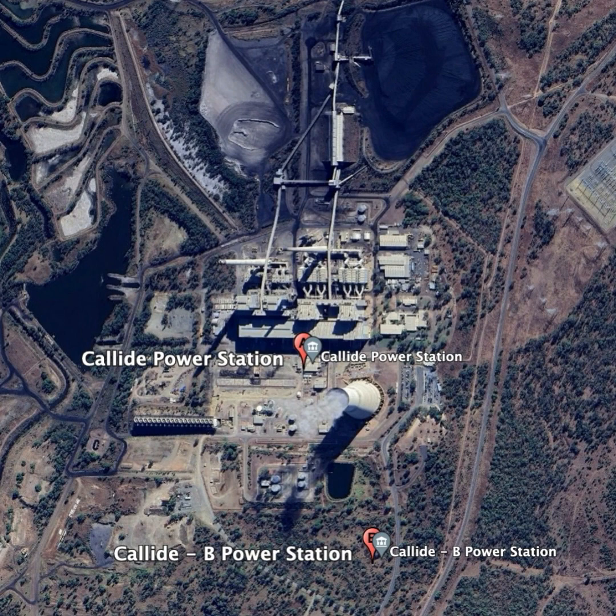The generator was now experiencing high temperature arcing between the rotor and the stator, ionizing the copper, and was now sinking 300 megawatts and 1400 megavars from the grid, which was 3 times its actual power rating. This dragged down the line voltage at Callide substation, resulting in reactor and capacitor banks being switched in to compensate. Callide Unit B2 then also tripped. After 40 seconds of arcing in Unit C4, a phase-to-phase fault dropped the A and B phase voltages severely at the Callide substation. The following events happened in a time span of less than 60 seconds.